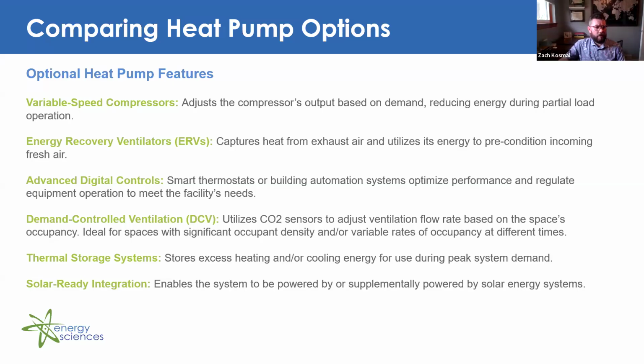In addition, an ERV or energy recovery ventilator would be especially useful in a building with high occupancy or a very tight building envelope where ventilation is critical, but the losses can be minimized by having some of that waste heat recovery within your energy recovery ventilator. Sometimes those could be referred to as a heat wheel. It's just a mechanism for capturing that exhaust air to precondition your incoming fresh air. So in summary, unique situations within a facility may provide the right opportunity to utilize specific heat pump options. So just keep that in mind when you're sifting through all of these heat pump options.